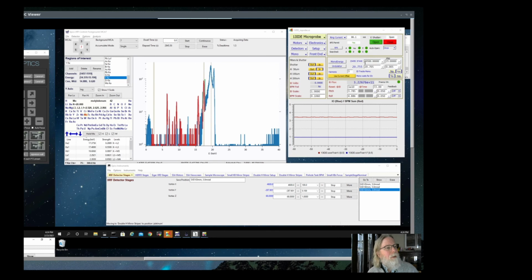Here we also have, down below, the energy of the monochromator, currently around 20 keV, and some information about the undulator settings that you shouldn't need to worry about. But then the next box down, we have the I0 flux, the flux hitting the sample as measured in that ion chamber between the slits and the mirrors, and that's reading in at 3 times 10 to the 11, which is a proper kind of flux for most acquisitions.